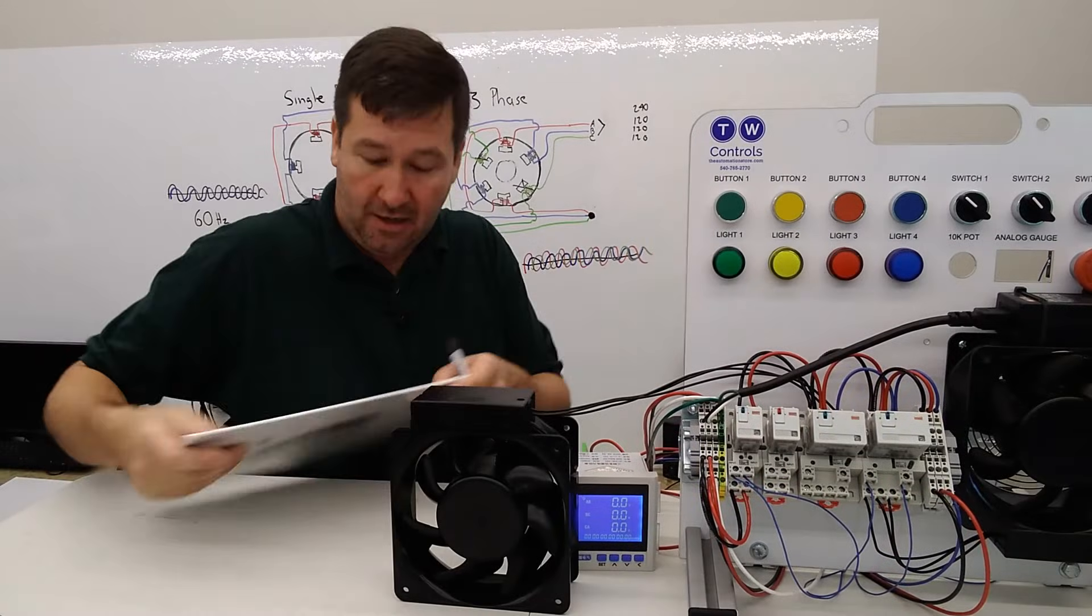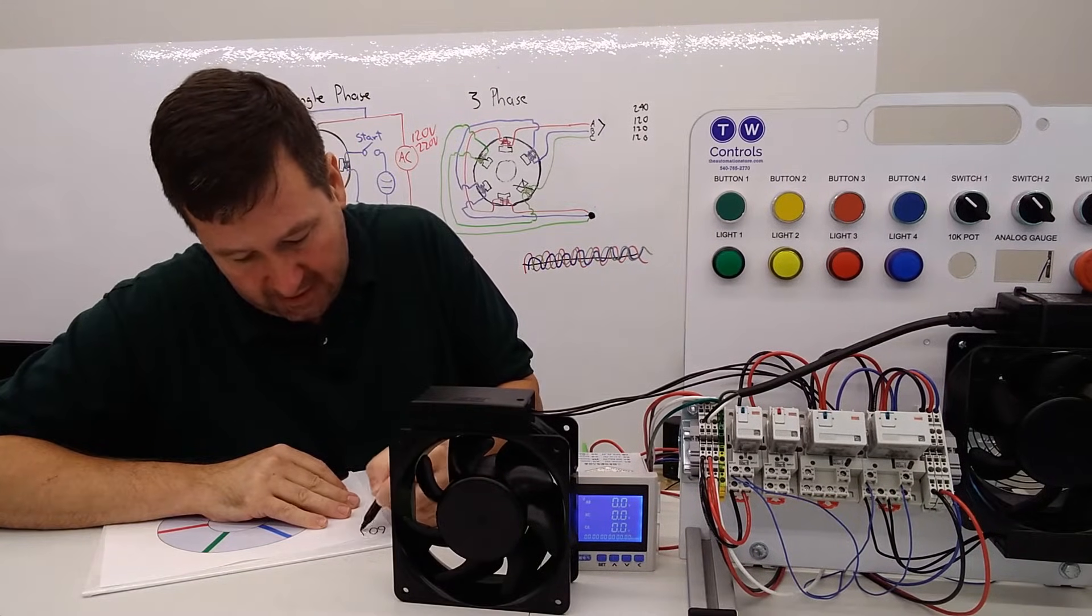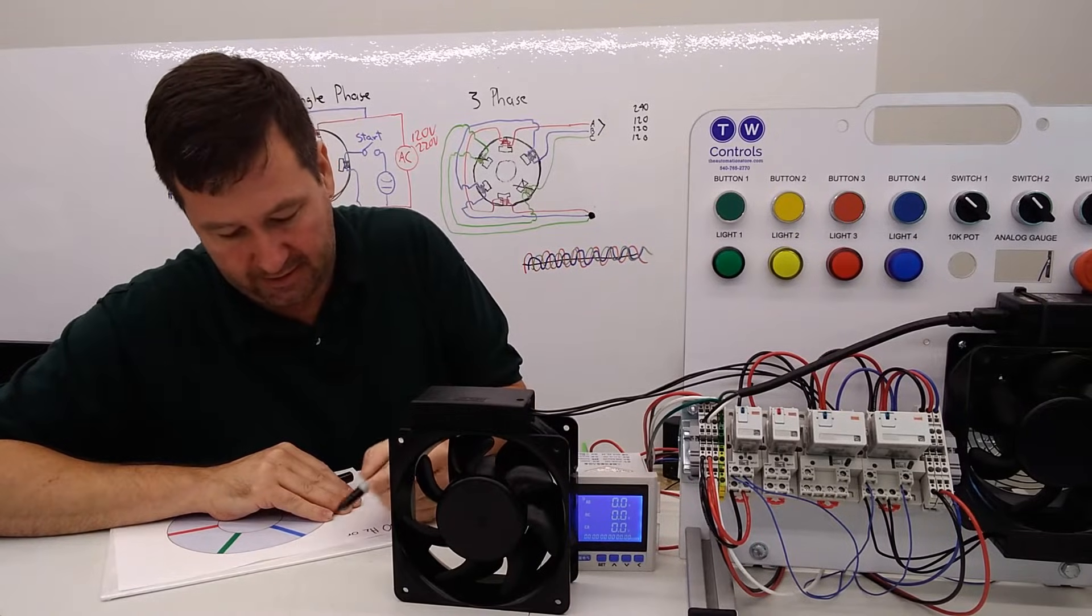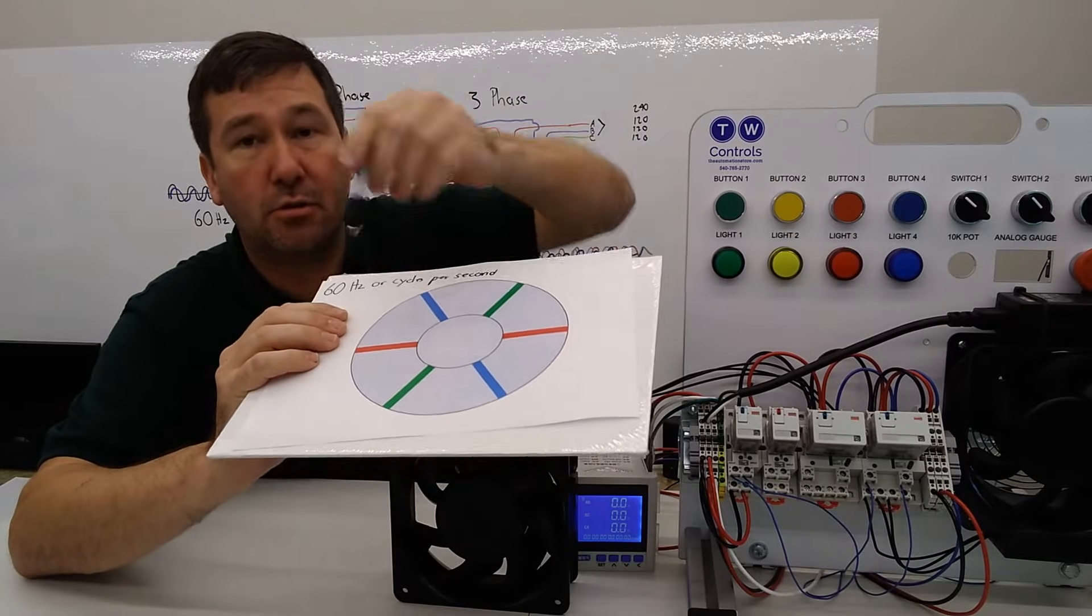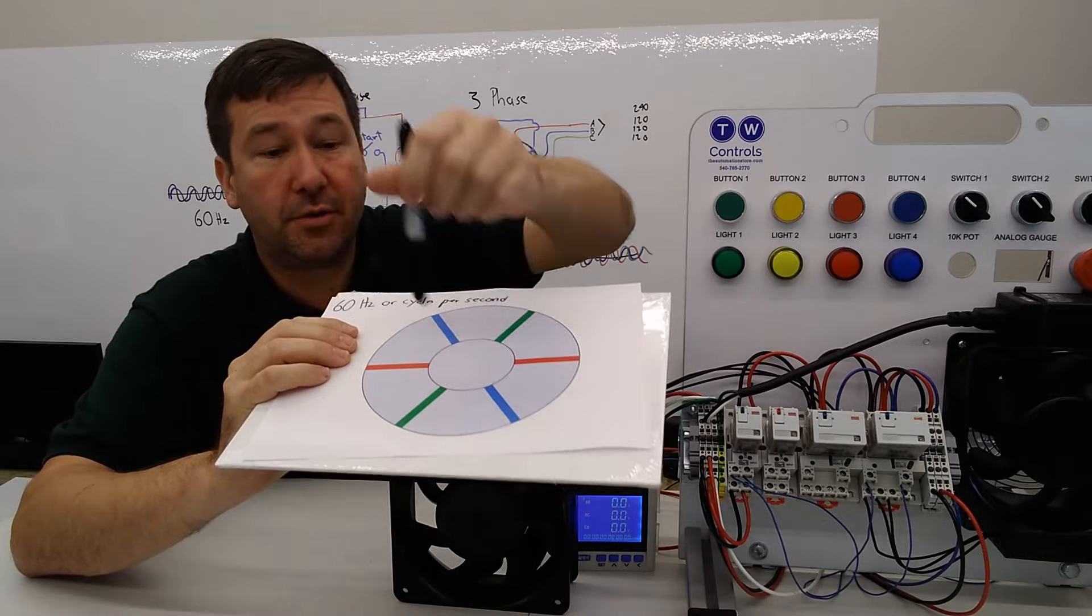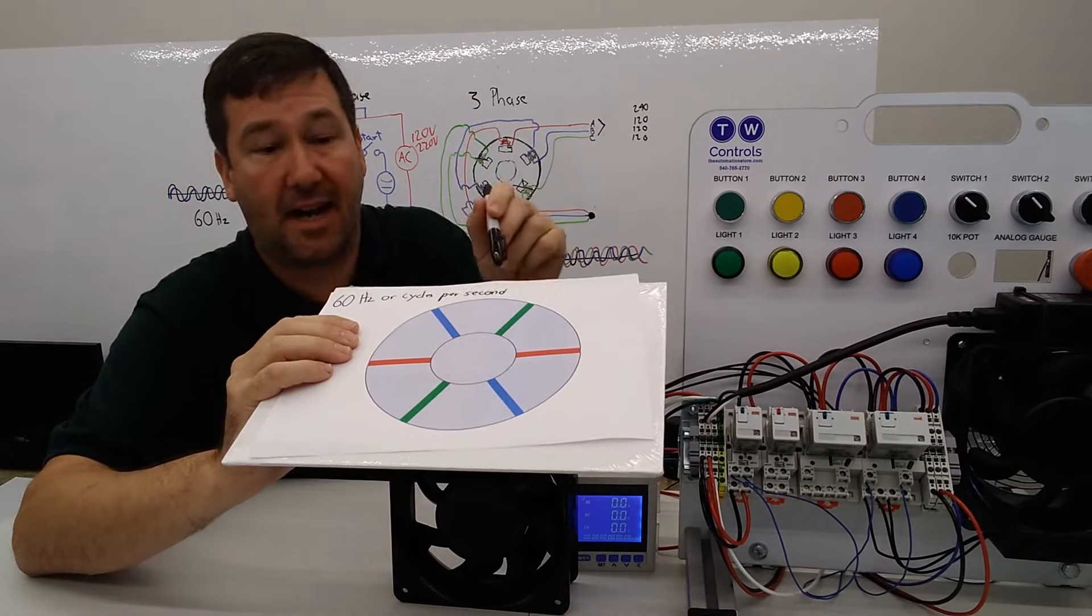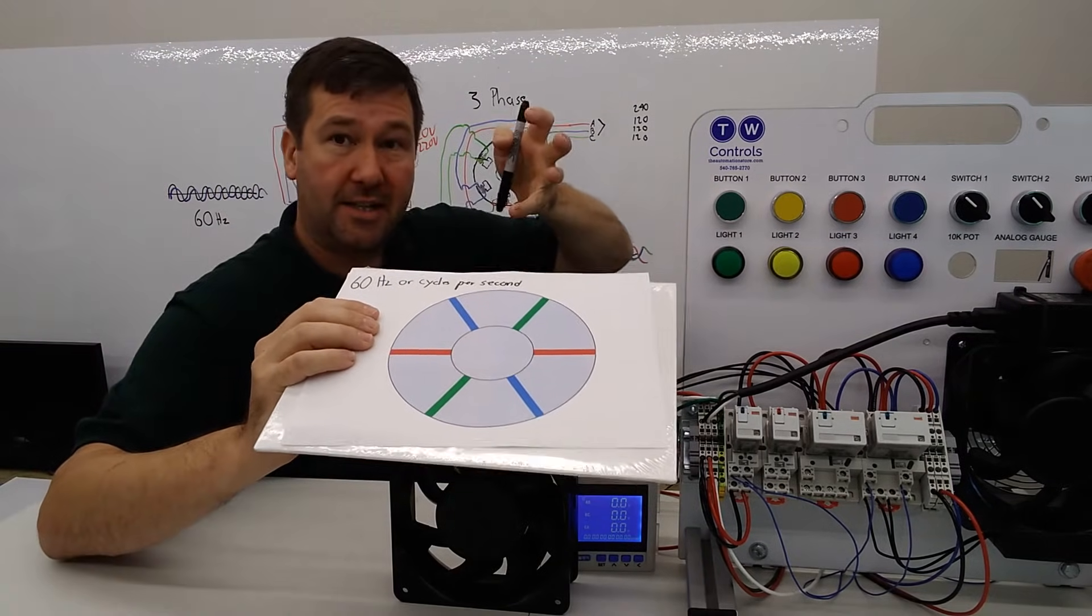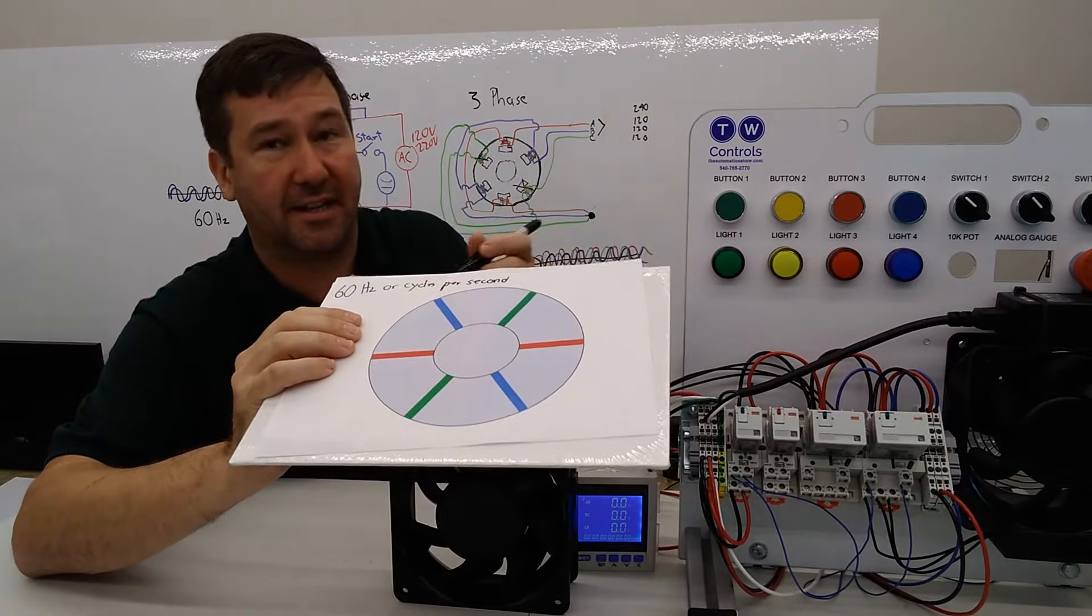So in the United States, we have 60 hertz, and 60 hertz is 60 cycles per second. So we have 60 cycles per second, and then this is a two-pole motor. So a two-pole motor is going to go north-south, north-south, north-south, 60 times per second. That means this rotating magnetic field, which is tied to our squirrel cage, is rotating 60 cycles per second.